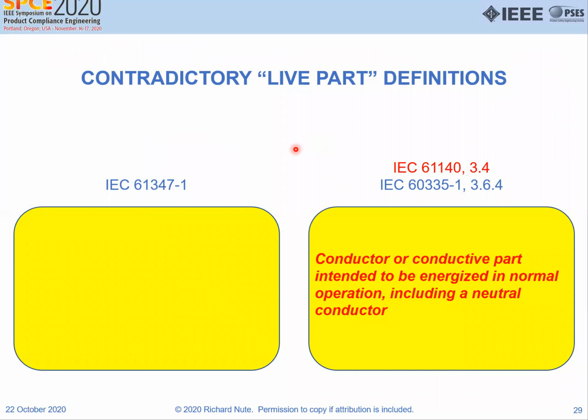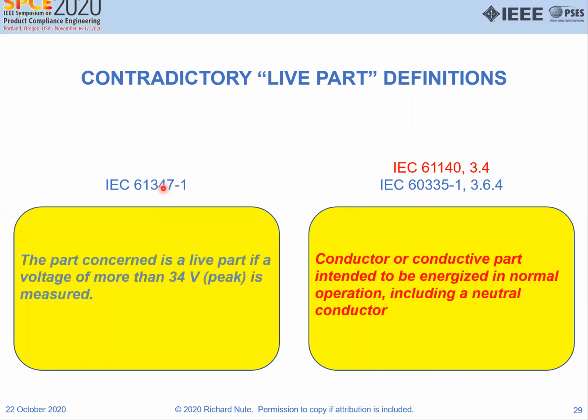But 1347 is contradictory to 1140. 1140 says a live part is a conductive part intended to be energized in normal operation. And 1347 says the part concerned is a live part if a voltage of more than 34 volts peak is measured. So it's contradictory.